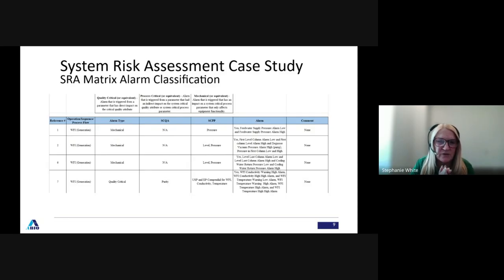So they were mechanical alarms, and I listed them. We noted that they don't impact a system quality attribute, but they do impact a system process parameter, such as pressure or level. The one that was quality critical was purity, our system's critical quality attribute, which requires following USP and compendial standards for conductivity and temperature.